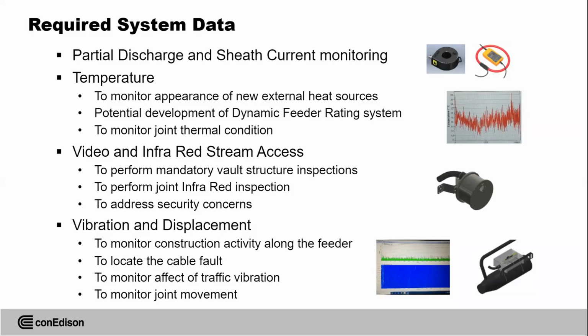And then you can investigate and adjust your maximum rating, especially when we're talking about purely transmission feeders, where load can go either direction, connecting bus to bus. Those feeders sometimes need to be used to the maximum of their ability. It doesn't matter whether it's for 3 hours, 20 minutes, or 300 hours. We're using 300 hours as one of the parameters in our system.